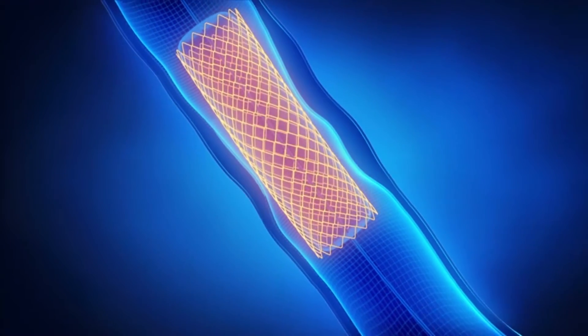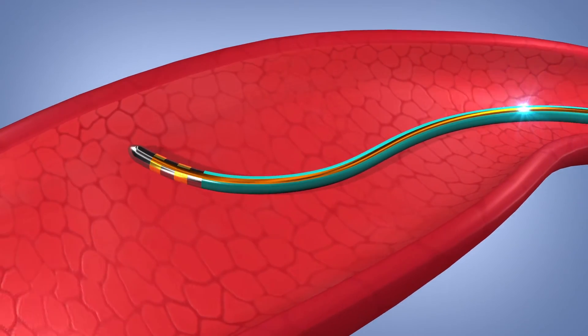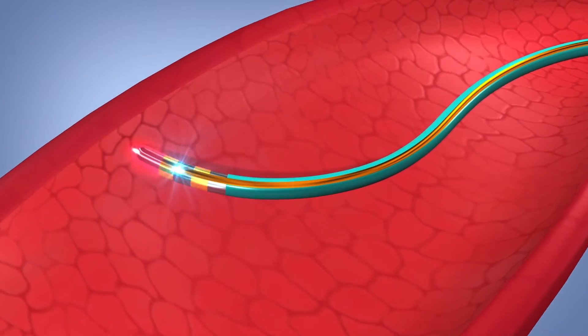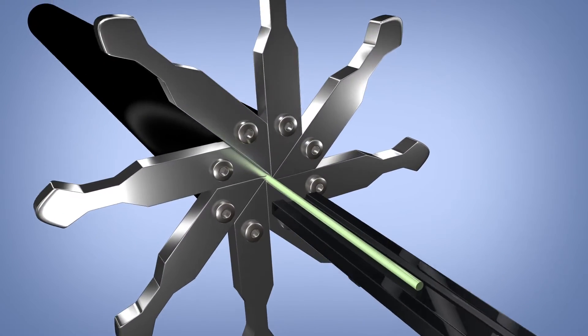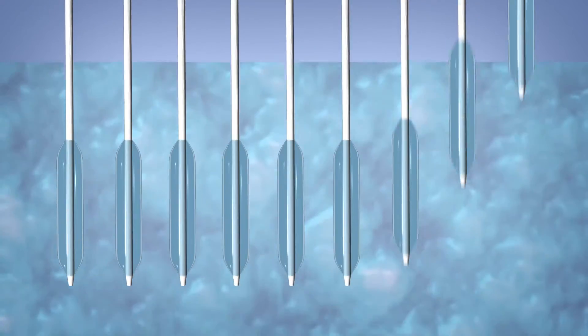With the utilization of ProPlate's MetaPoly coating, manufacturers can precisely add radiopaque marker bands and current conducting paths onto polymers. Whereas traditional markers and conducting wires are often laboriously installed into devices, the MetaPoly process can be accomplished in large volumes simultaneously.